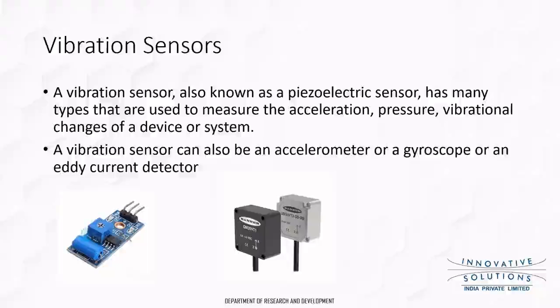We may have heard of the term preventive maintenance. What preventive maintenance does is measure the vibration and other quantities of the machine, and before there is any fault, it will tell you that there may be a fault in this bearing after 10 days. It generates a trend of the vibrations and detects that this value may rise after 10 days, not today. Getting this advance warning that there may be a failure allows them to do the maintenance and avoid downtime. So we had this project for Bharat 4.